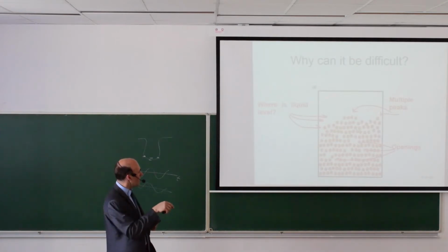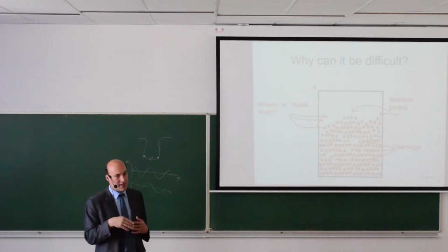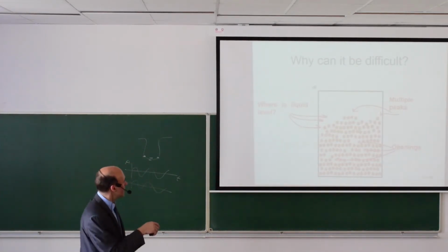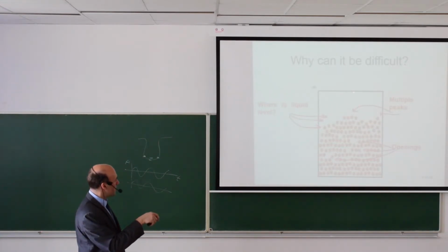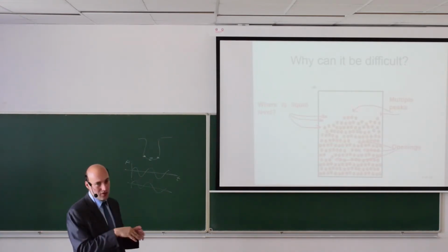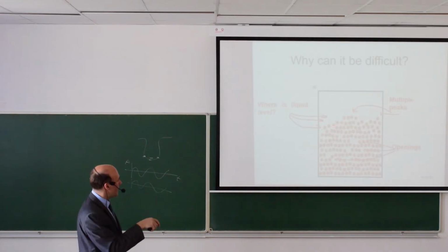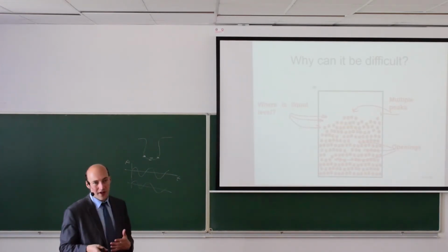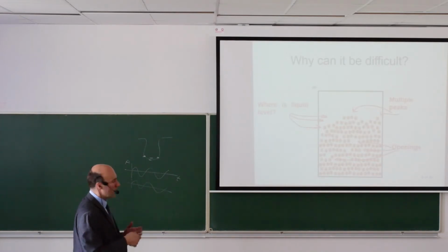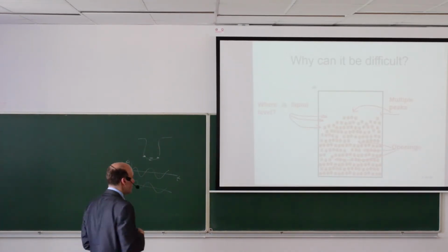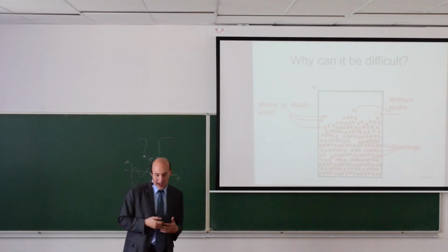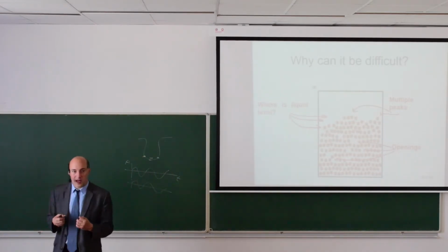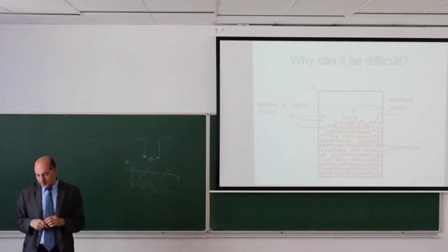If you look from the top with a distance sensor on this, then where should you measure? You should measure here on the peak, okay, then you estimate a level, but then you miss this area where you don't have any material. So where is the level? You are trying to estimate what the level would be if it would be filled ideally.